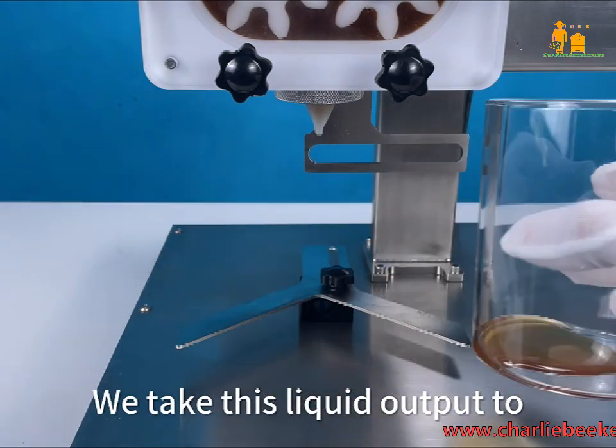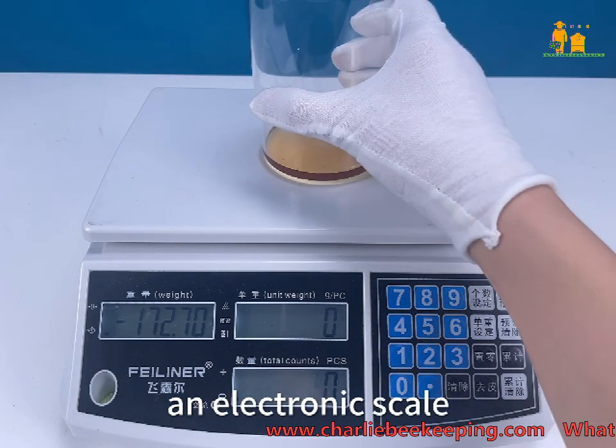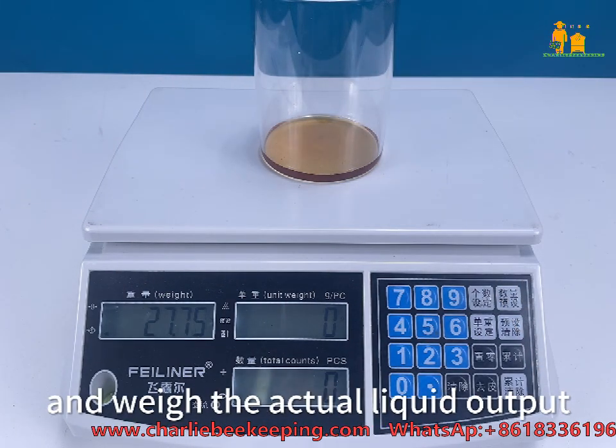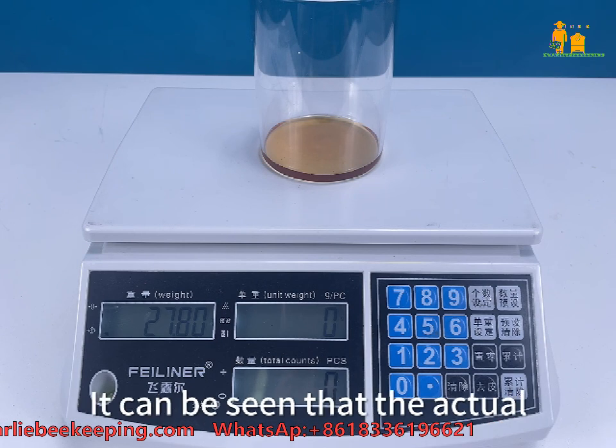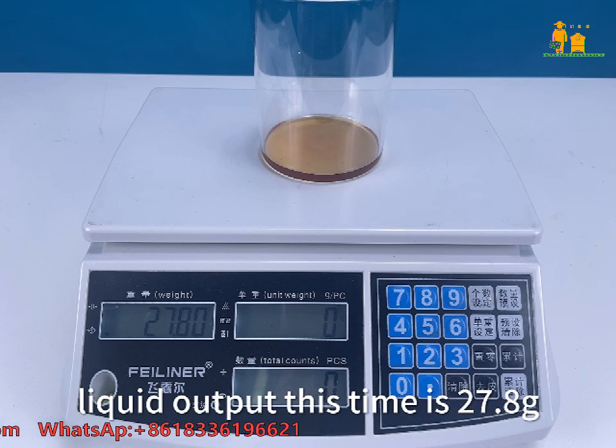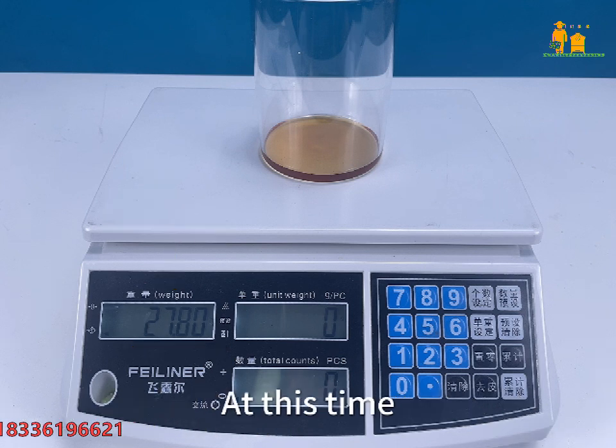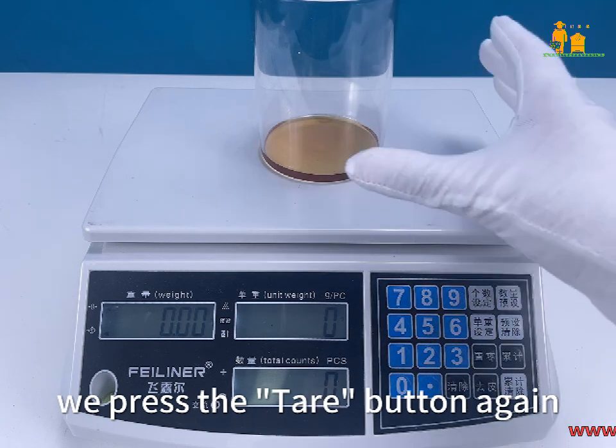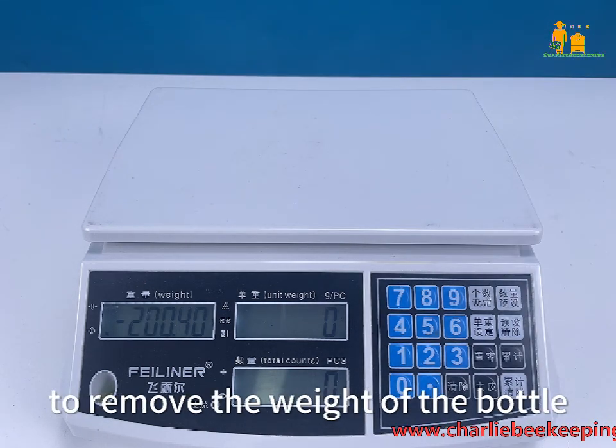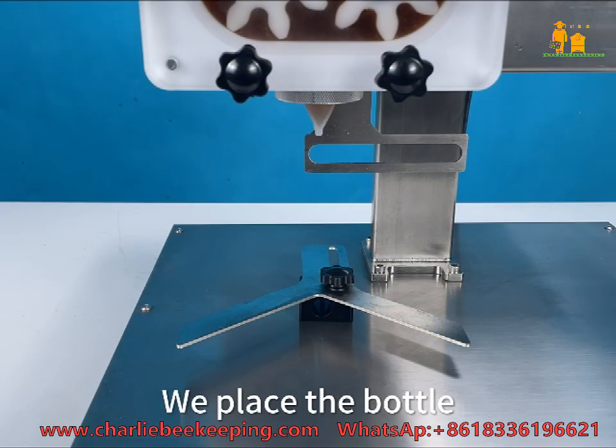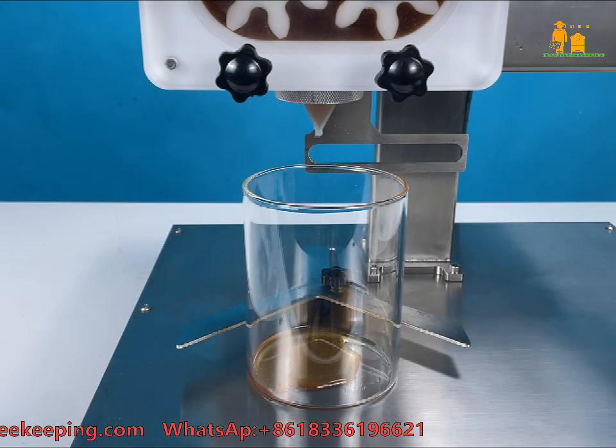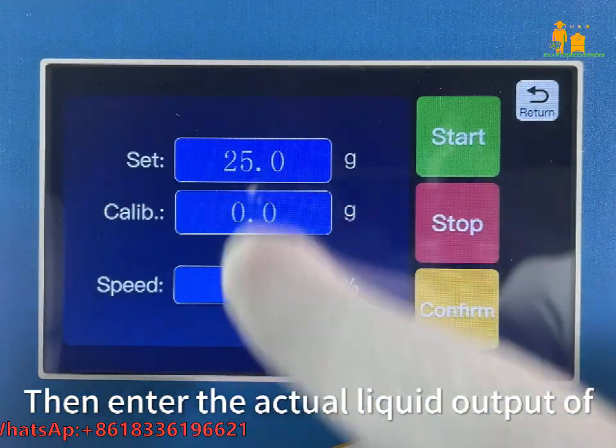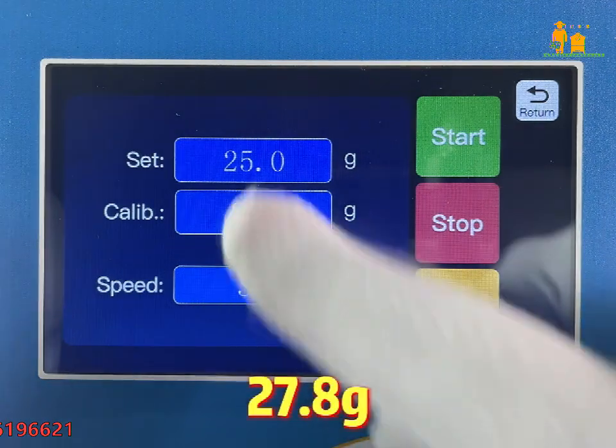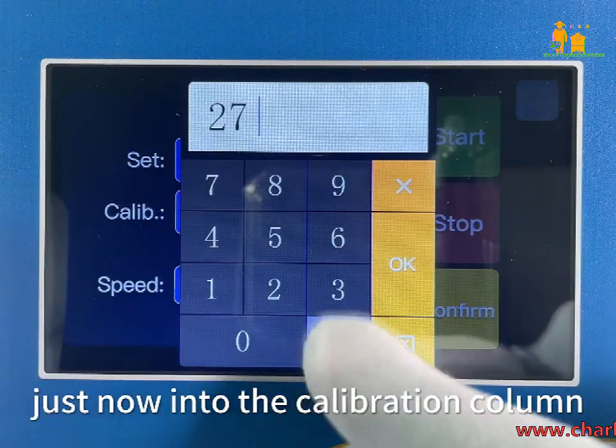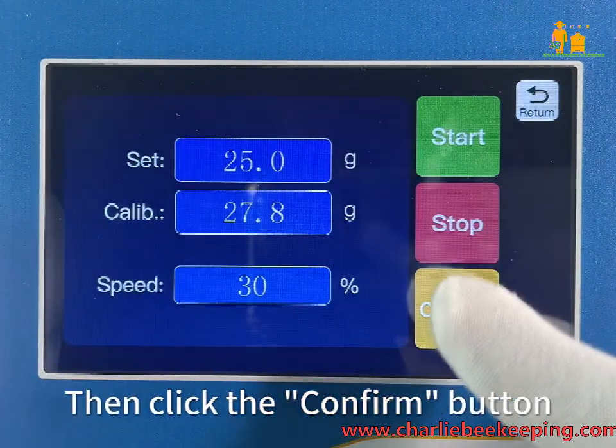We take this liquid output to an electronic scale and weigh the actual liquid output. It can be seen that the actual liquid output this time is 27.8 gram. At this time, we press the tare button again to remove the weight of the bottle and the liquid to prepare for the next weighing. We place the bottle again under the outlet. Then enter the actual liquid output of 27.8 gram just now into the calibration column. Then click the Confirm button.